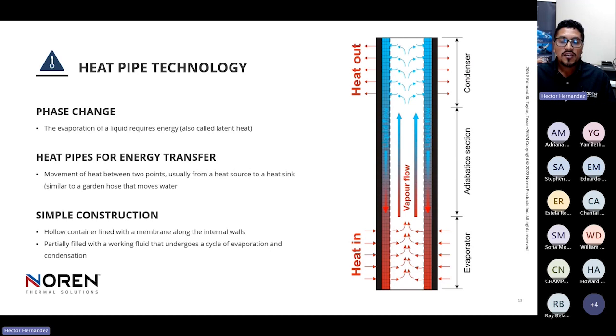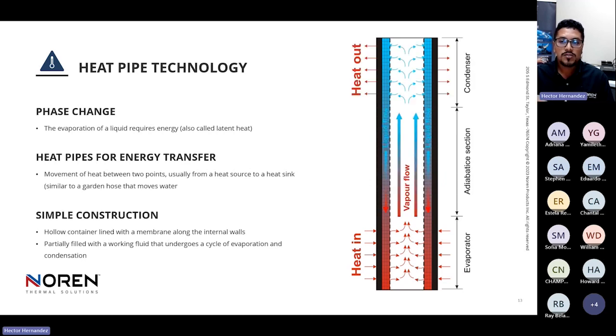On the opposite side, for an ambient cooling application, we have the ambient air. The ambient air is forced to pass through around the walls of the heat pipe. This air expels the heat, and the working fluid changes phase from vapor to liquid, returning to the bottom end thanks to gravity and capillary forces.